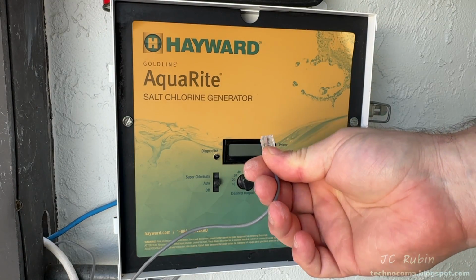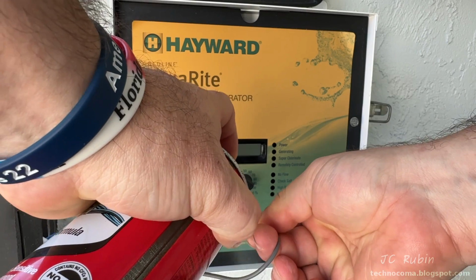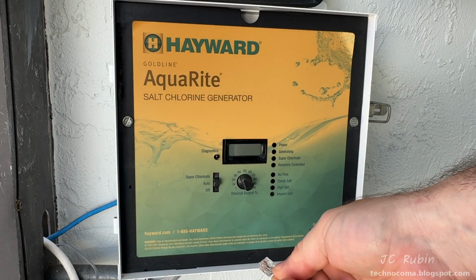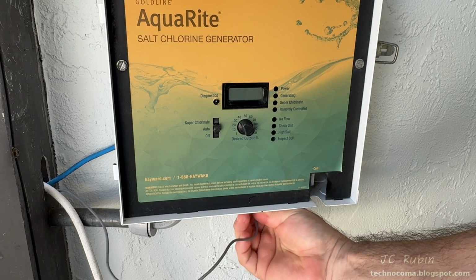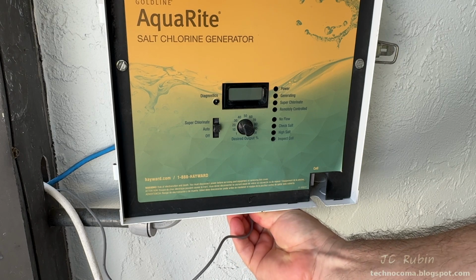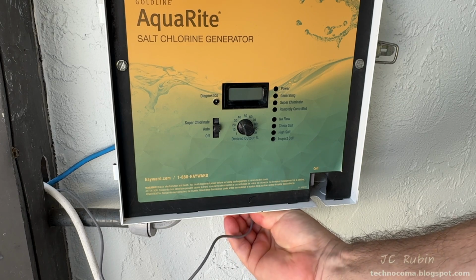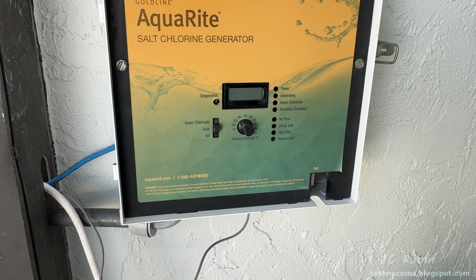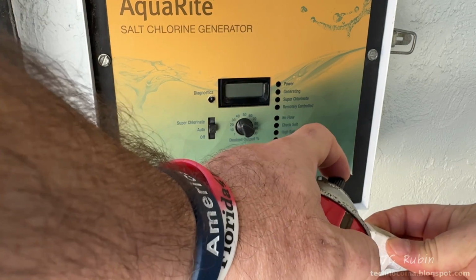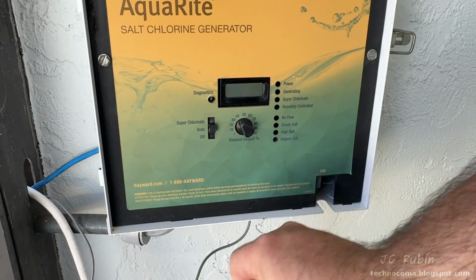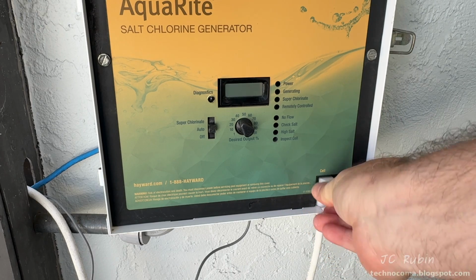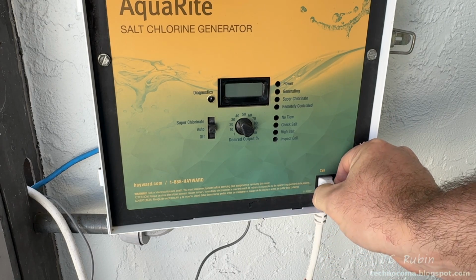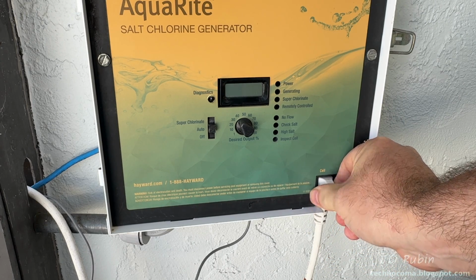I'll take a moment now to spray the flow sensor with some contact cleaner, and then install it several times into the unit to clean the wipers, then just leave it installed. I'll do the very same thing with the cable from the cell, installing it in and out several times with contact cleaner applied to clean up those connections.